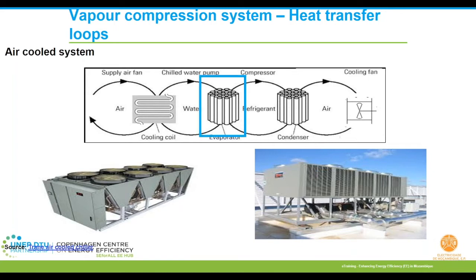As I've said, the fundamental components remain the same. In order to cater to larger areas, there would be no direct contact of air with the evaporator. Instead, you would be using water. The water gets cooled and this chilled water is circulated to the user ends, such as air handling units or FCUs. On the condenser side, heat exchange is still done with air, only that you have large banks of fans instead of smaller ones, unlike conventional residential or smaller capacity air conditioning units, to reject the heat from the refrigerant.